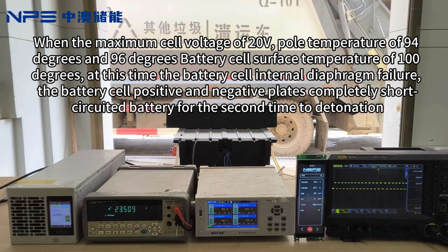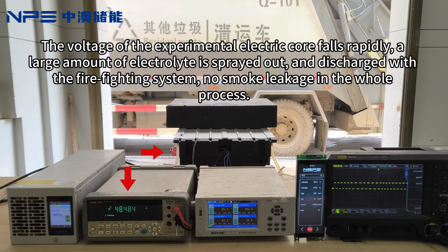When the battery cell voltage reaches a maximum of 20 volts, the battery pole temperature is 94 to 96 degrees, and the battery cell surface temperature reaches 100 degrees. At this time, the battery cell's internal diaphragm fails and the positive and negative plates are completely short-circuited. The battery experienced a second leakage explosion. During the experiment, the battery cell voltage dropped rapidly. A large amount of electrolyte sprayed out and was discharged with the fire system cycle, with no smoke leakage in the whole process.